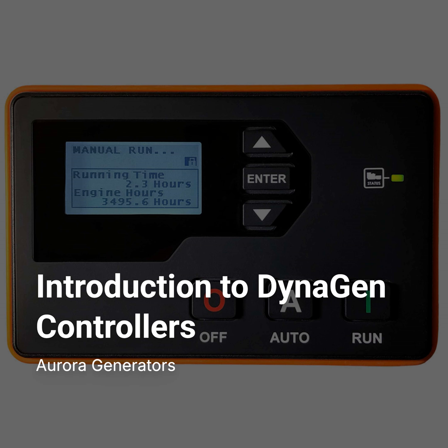Interesting feature. And of course, the most fundamental safety feature, emergency stop. Absolutely essential. An external e-stop switch is mandatory. It has to be wired to directly cut the fuel or ignition supply. It provides that immediate, reliable shutdown for emergencies. Okay, makes sense. We've covered real-time operation and immediate protection. What about time-dependent functions? Timers, scheduling.